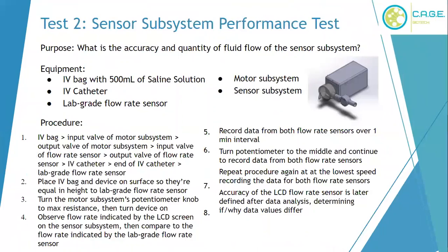The second test was the sensor subsystem performance test, which tested the quantity and accuracy of fluid flow of the sensor subsystem, and the procedure also takes into account the motor subsystem. The setup has the IV bag connected to the input valve of the motor subsystem. The output valve of the motor subsystem is hooked up to the input valve of the flow rate sensor. The output valve of the flow rate sensor is connected to the IV catheter, and the end of the IV catheter is connected to a lab-grade flow rate sensor.